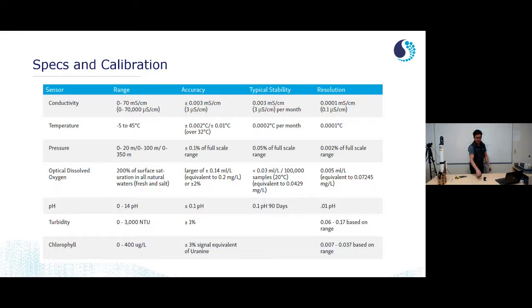This has a special pH sensor, this guy right here — a glass electrode pH sensor. This is different from sensors like the CFET V2 and the CFOX V2, in that it uses a different kind of sensing technology. As such, the accuracy of this is 0.1 pH, and it retains its stability of 0.1 pH for approximately 90 days. So that's something to keep in mind.